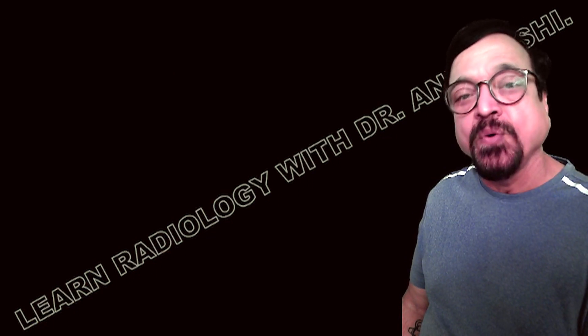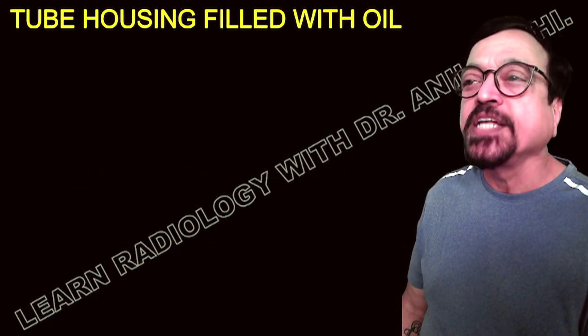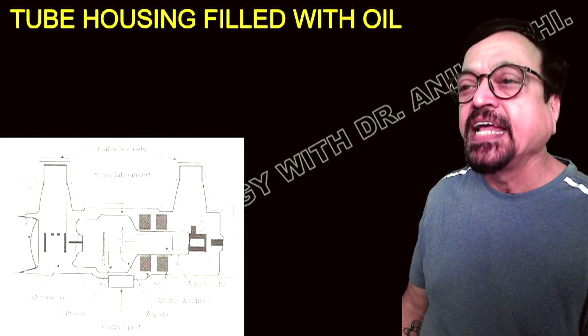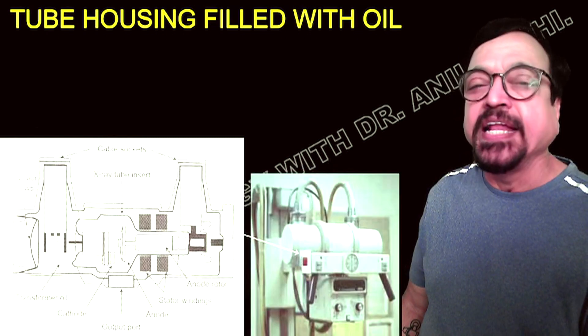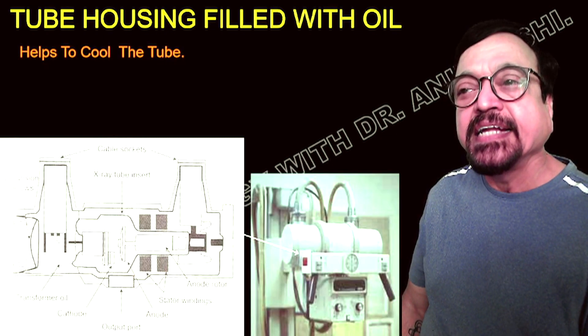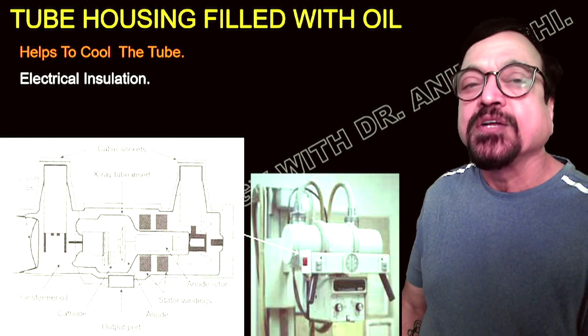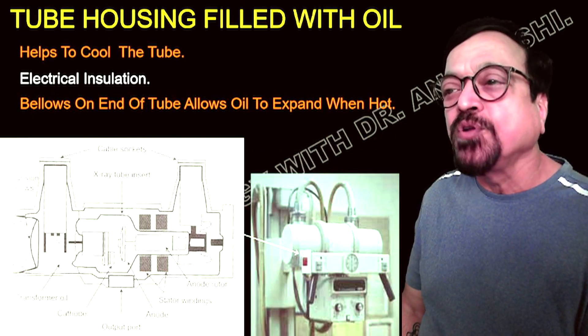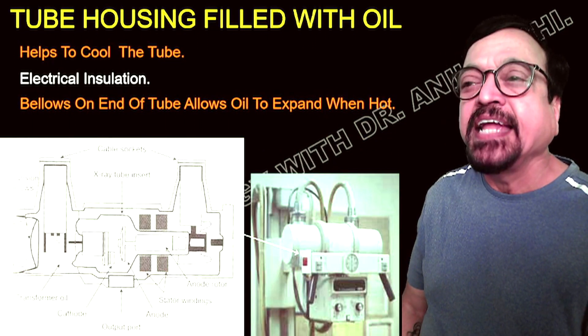The tube housing is also a heat protector. As mentioned, 99% of the energy is converted into heat and only 1% into x-rays. The tube housing is filled with oil. This oil dissipates the heat produced, helping to cool the tube. It also provides electrical insulation. At the end of the tube there is a bellows that allows the oil to expand when heated.